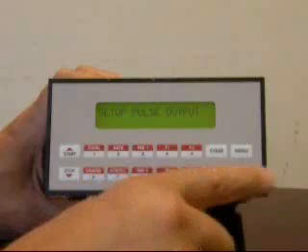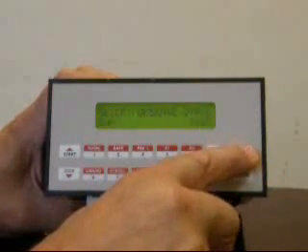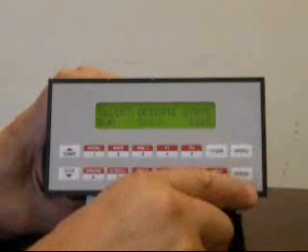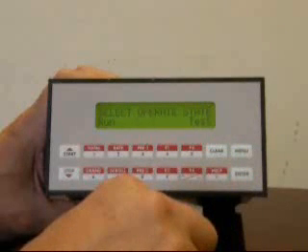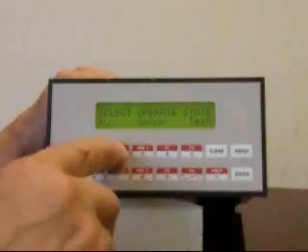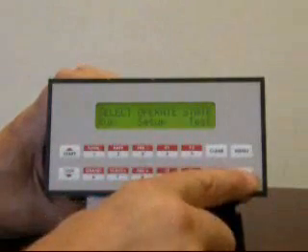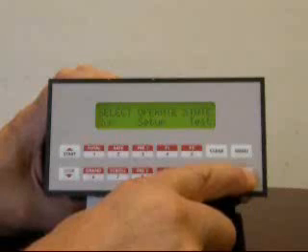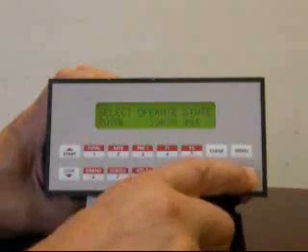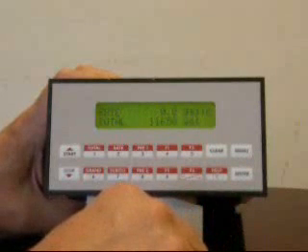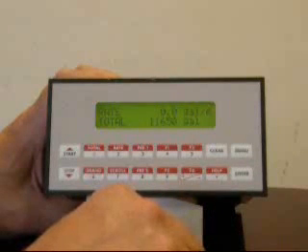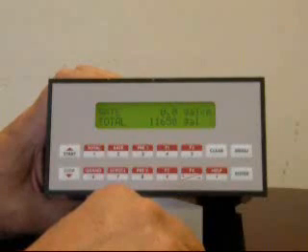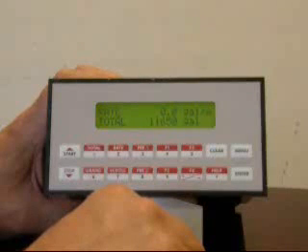To escape out of the menu mode, you press menu to return to the selection that says run setup and test and choose the run mode. Pressing enter will return you to the run mode. The unit is now fully configured for the basic application with a turbine flow meter measuring in gallons per minute and gallons for use with a magnetic pickup. For additional menu selections on the other outputs, please refer to the user manual and make changes as needed.